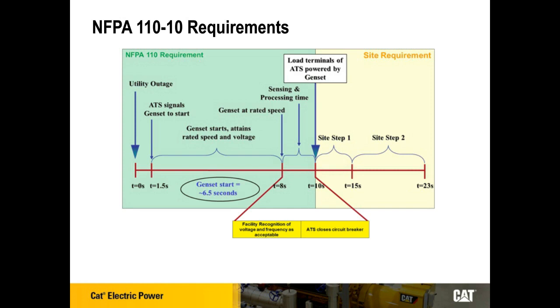Something that's also commonly interpreted for NFPA 110 is you might see an AHJ with a stopwatch at a job site waiting for the light. They'll kill the power from the utility and then wait for the lights to come on. That usually works okay, but the letter of NFPA 110 just requires the power to be available on the load terminals of the transfer switch within 10 seconds. So depending on the type of lighting at the site and the power distribution, the lights may add some other delay that's not a part of NFPA 110.